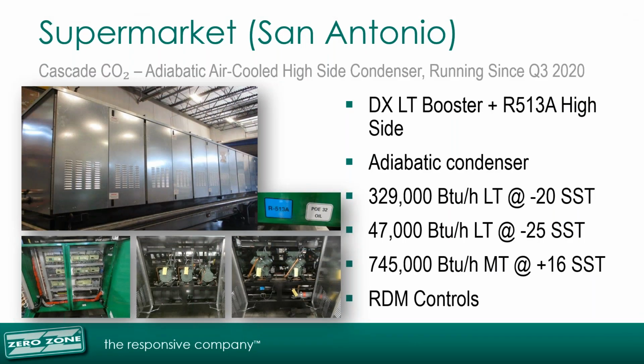This is the last example of the subcritical CO2 systems. This is an outdoor parallel system, OPS for short, that is using R513A as the high side refrigerant for the medium temperature circuits and to provide cooling/condensing for the low temperature CO2 system. It has a welded steel frame with lift-up pneumatic actuators and is ready to be picked up and set on a roof pad.